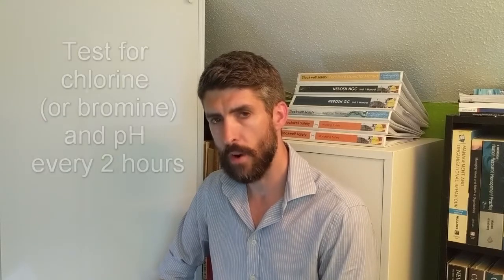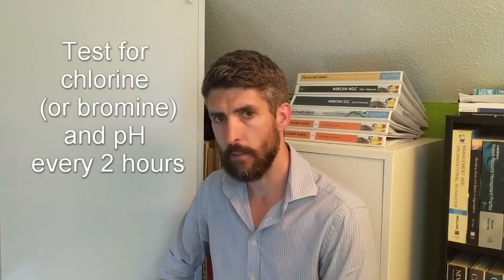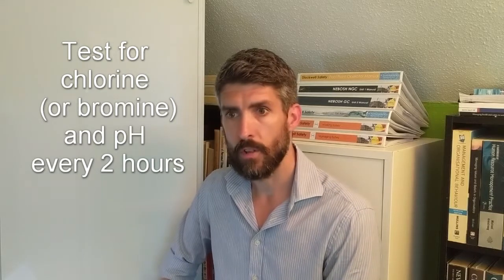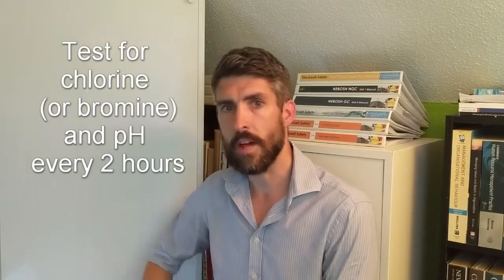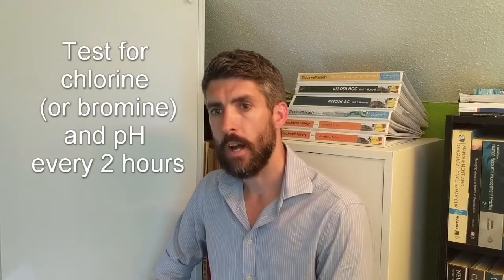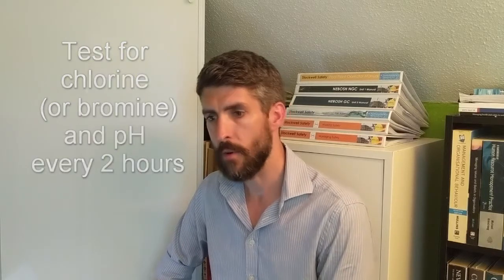With spa pools, what you need to do is test the chlorine and the pH levels every 2 hours, and that is even with an automatic controlled chemical dosing system. It's a 2-hour frequency, which is more frequent than swimming pools would typically do it, because things can change quite rapidly in a spa pool. Because of the low volume of water there, it really doesn't take much to get the chemical levels out of whack.